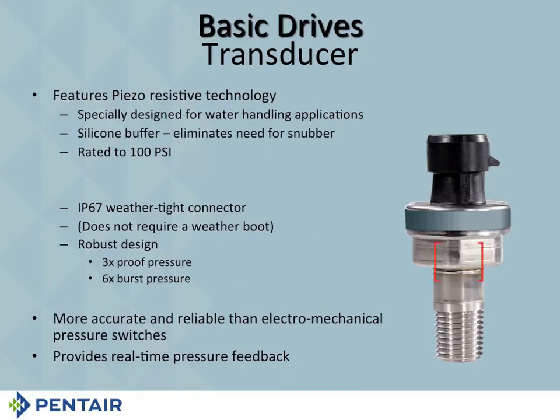All right. Right in that area there where you see the red square on the transducer, there is a plug in there. That plug prevents the water from actually touching the diaphragm. And what that does is that protects the diaphragm. So if you've got a bad water application, this will help to prevent that bad water from corroding or having problems with the diaphragm and so forth.